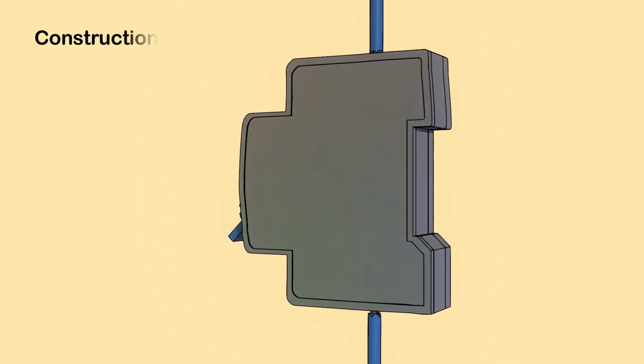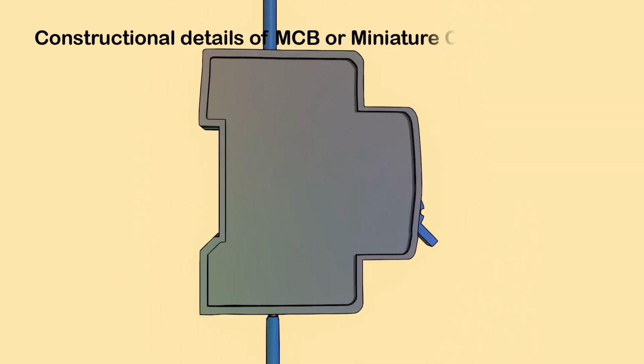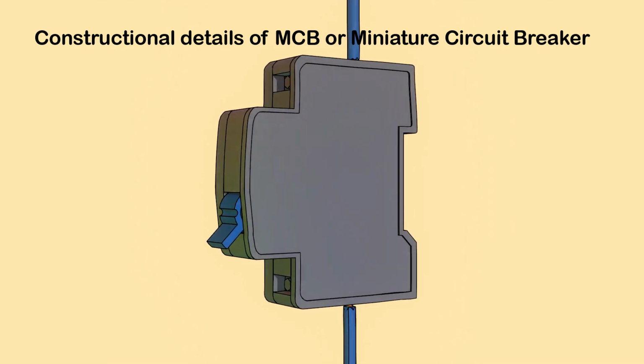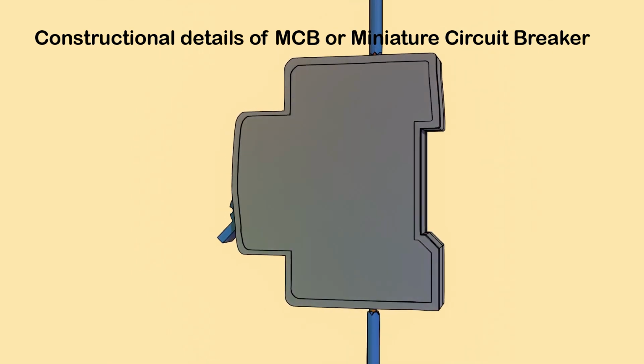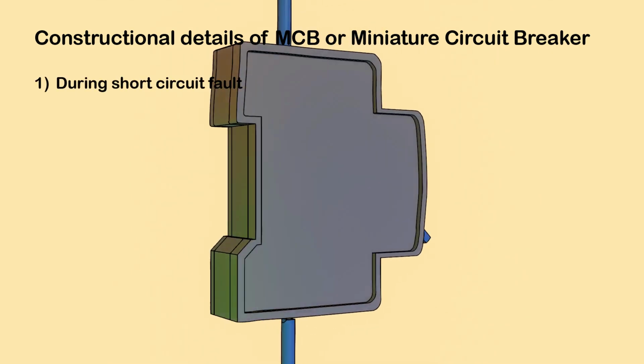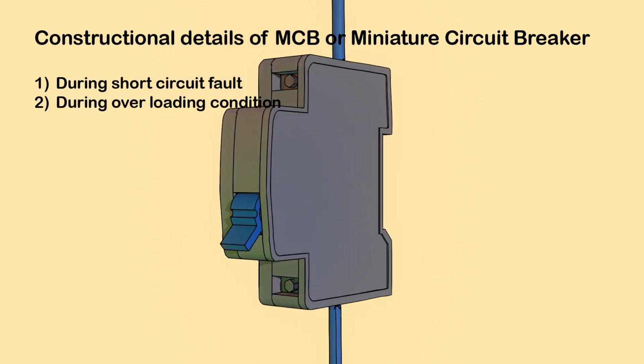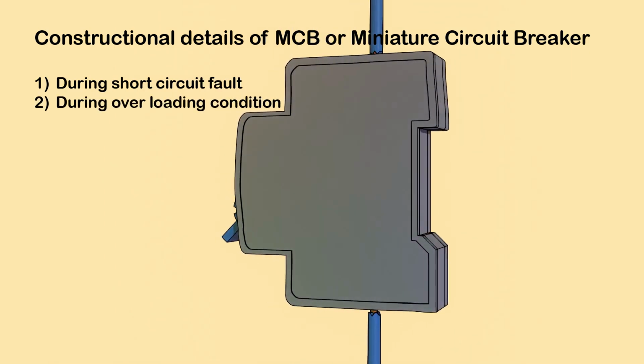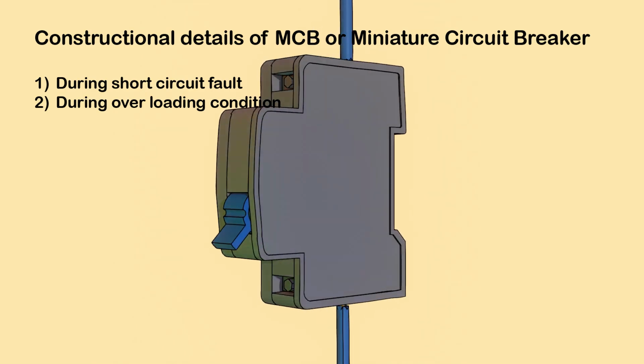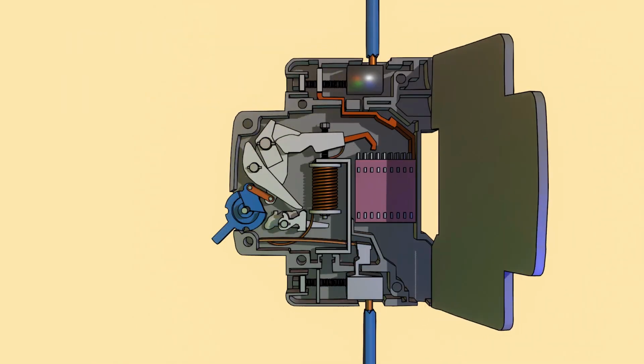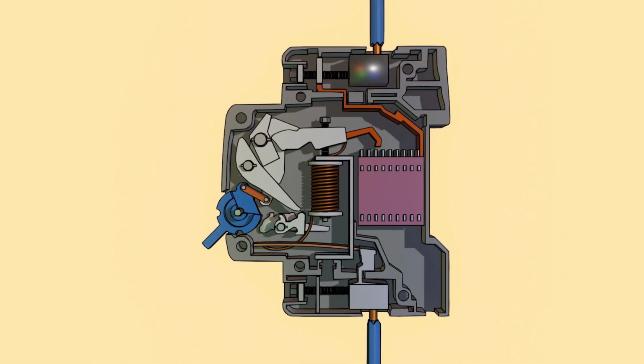Let's have a discussion on the constructional details of an MCB, or a miniature circuit breaker. It works on two major principles. One is during a short circuit fault, two is during an overloading condition of the circuit. In both cases, a miniature circuit breaker trips the circuit. For that, it has two arrangements.